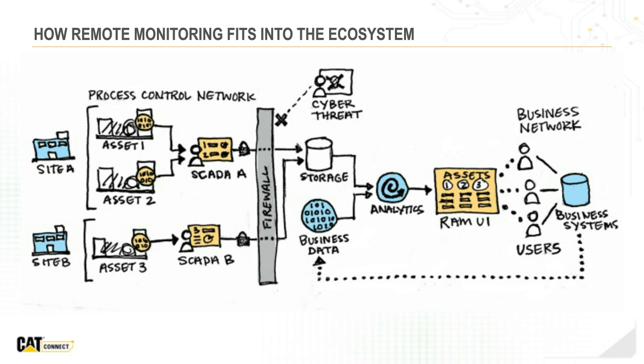Typically, SCADA systems have the ability to trend some of that data, but it's usually a limited amount, maybe around 30 days. And it's really more about alarms and alerts tied to the limits set within the control system.